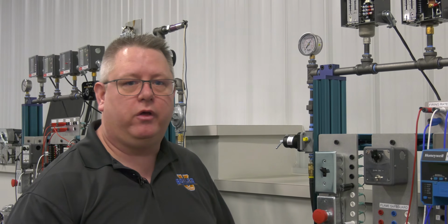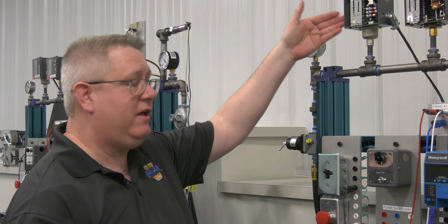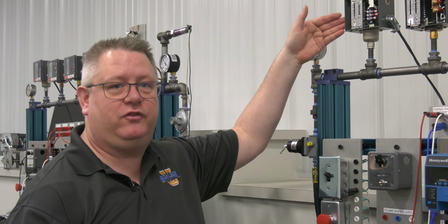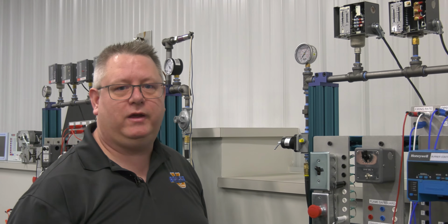So that's going to give us a really stable burner operation, and there's no harm in running a boiler that's rated for that pressure up to that higher pressure before shutting the boiler down. But it's not the firing rate's job to shut the boiler down, it's the operator, and we'll talk about that next week.